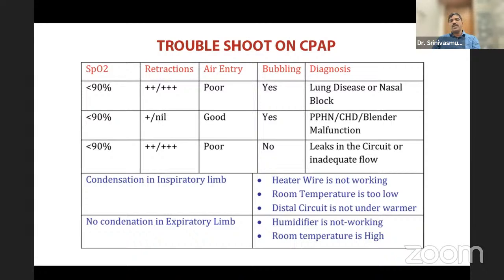Regarding the humidification, if you see condensation in the inspirate limb, that means your temperatures are so low. These machines are likely to work in a temperature of 26 to 30. So the humidifier is likely to work best in 26 to 30, or your inspirate limb heater wire is exposed to the radiant warmer. That also can be a reason for condensation in the inspirate limb. So you cover that distal part of the inspirate limb with a gauze or avoid the radiant warmer coming on that. So if there is no condensation in the expirate limb, you should expect some moisture in the expirate limb.